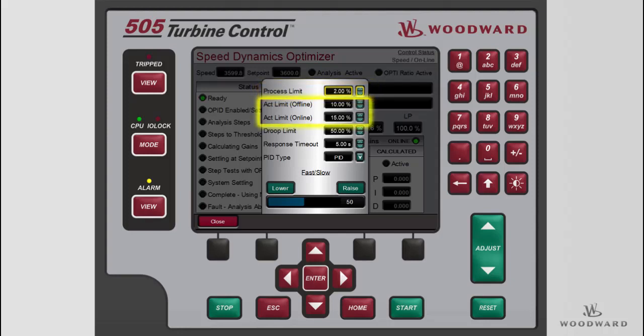The online and offline actuator limits set how much the actuator demand will move during the analysis mode. The percentage will limit the output plus or minus from the actuator position when the optimizer test is enabled. The test will not abort if this limit is reached, but an alarm will be enunciated. It is important to note that the actuator limit is the most the actuator is allowed to move during the test, but may never reach this level. Because actuator movements start small and progressively increase, only the amount of actuator movement needed to analyze the system is used.